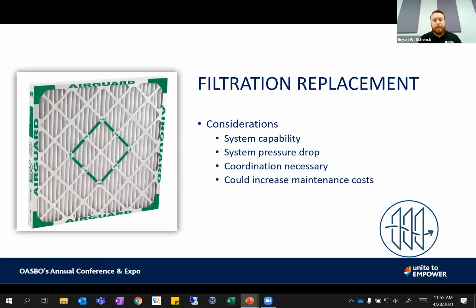So, system compatibility, I talked about that a little bit. What's the system pressure drop? What does that create, and what does that do within our systems that might create other changes to our mechanical equipment? Coordinate with your mechanical contractors, and consider the increased maintenance costs and lead time. If you want to upgrade to a higher MERV filter, is there a longer lead time to get that filter in? And what cost recurs if you're already changing your filters three or four times a year, and the additional cost that a higher MERV filter might have.